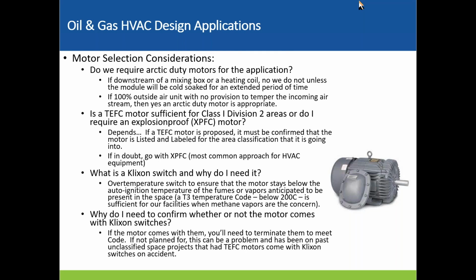One thing that comes up occasionally is whether a totally enclosed fan cooled motor is sufficient for Class 1 Division 2 areas, or whether you have to use an explosion proof motor. That kind of depends. A lot of times you'll receive a TEFC motor, but it won't say that it's suitable for Class 1 Div 2 Group D areas, Group D being methane. So then we end up sending the motor back and getting a new one. Ultimately, about three quarters of the time, I've seen it just get changed out for an explosion proof motor. So it's something to be wary of as you're doing your design.